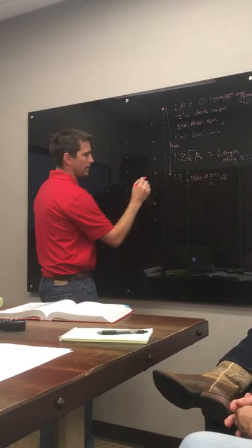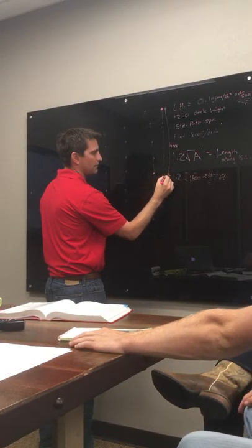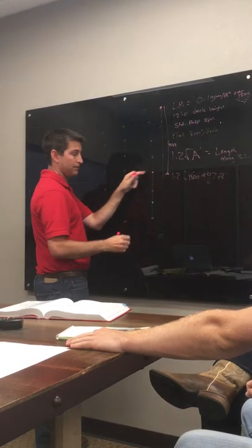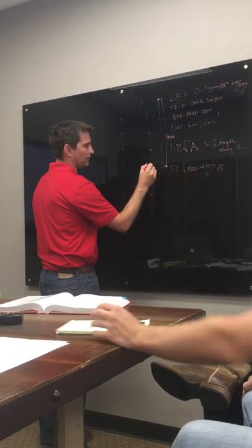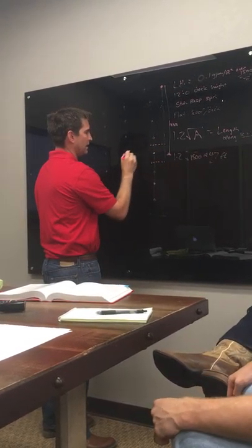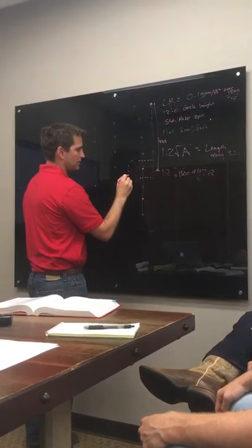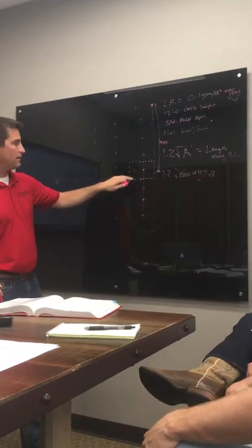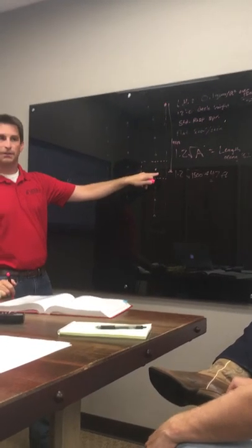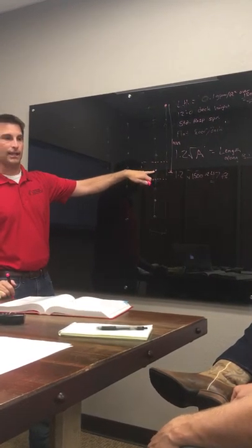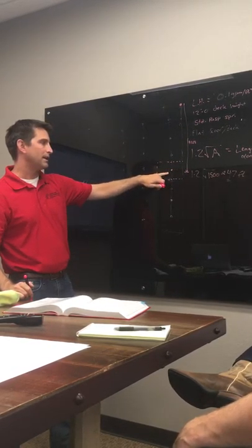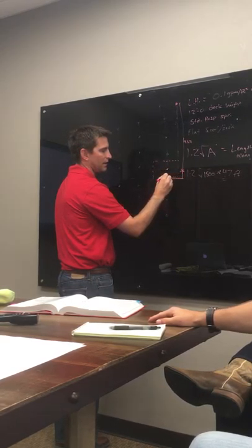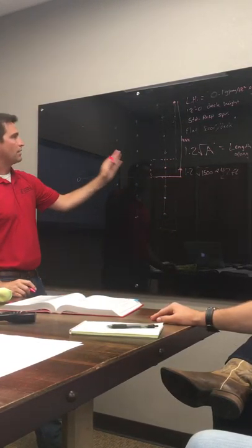But this is where it's important. If we looked at this sprinkler, let's say 47 feet was right here, just a little bit past that sprinkler. Well, that sprinkler itself sprays halfway to this sprinkler and halfway between those. So in all reality, that sprinkler is protecting that space, right? That is in the protection area of that sprinkler. So I want to take my remote area all the way to the edge of where that protects to. So 47 feet just fell just past there. I'd bring it to there, and that's where I would cut. And then I'd start moving back this way.